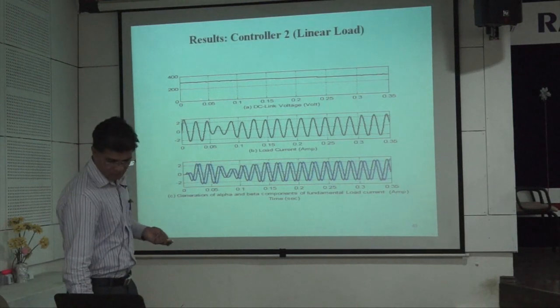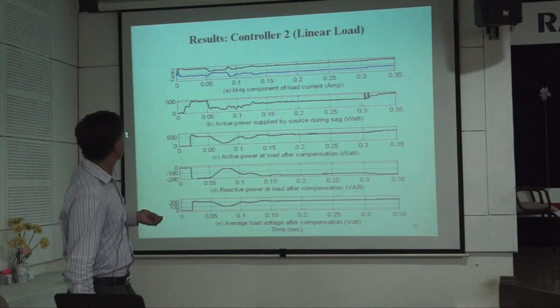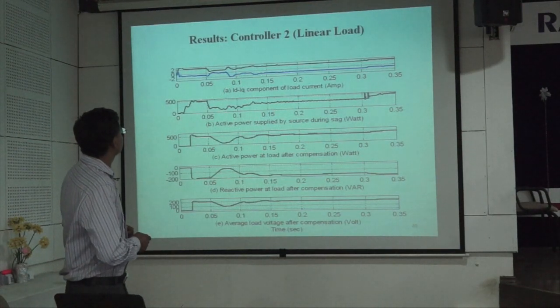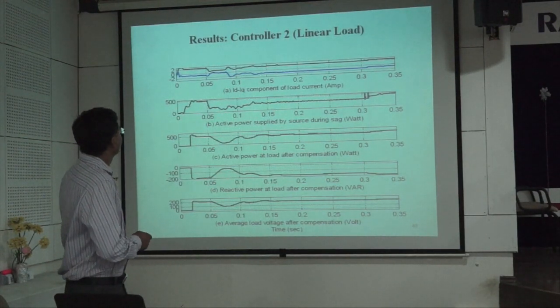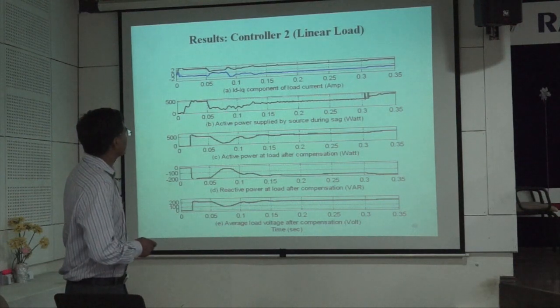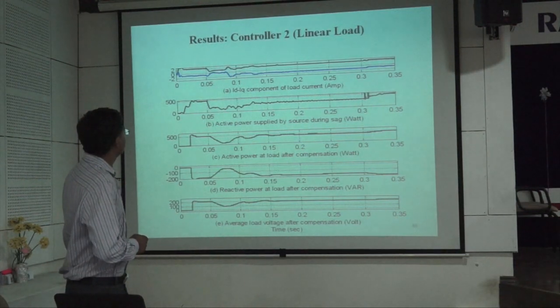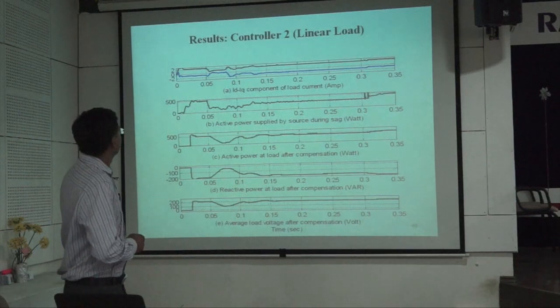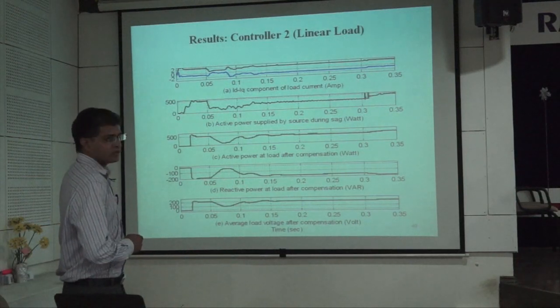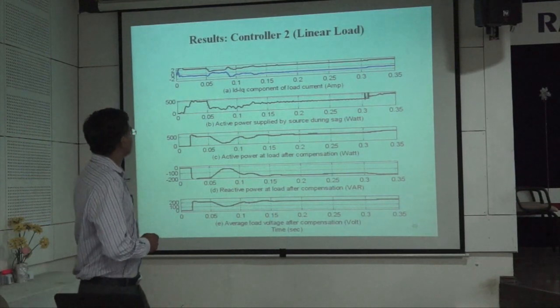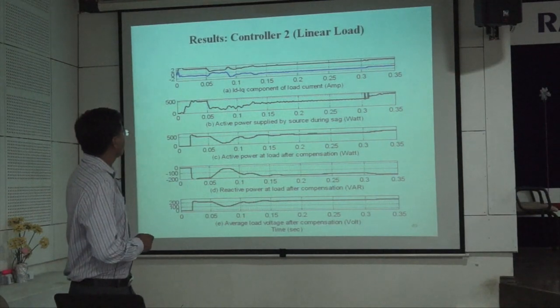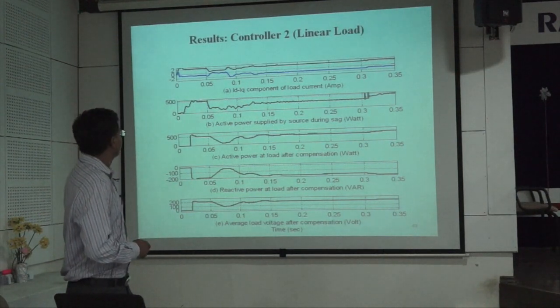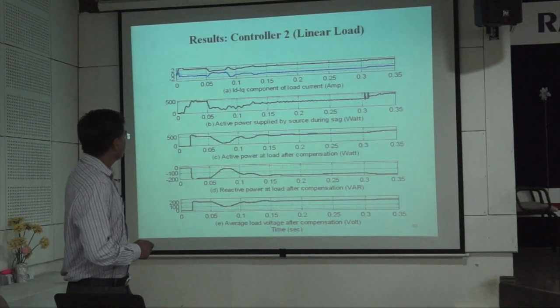Alpha beta components are generated with these. See the ID and IQ components. ID and IQ components are constant. So the active power supplied by the source during sag is decreased to 50%. Since 500 watt is the active power before the sag, after the sag it is decreased to 250 watt. So the DVR compensates 500 watt.